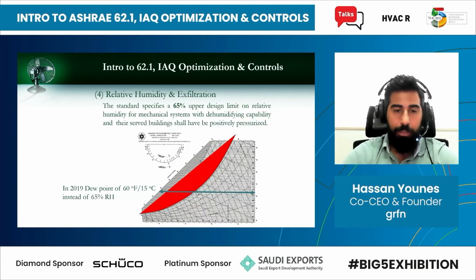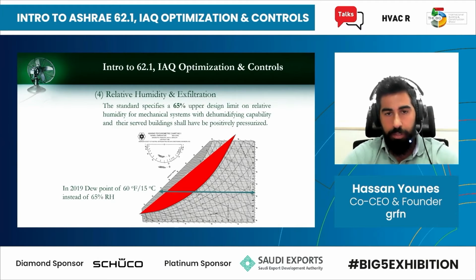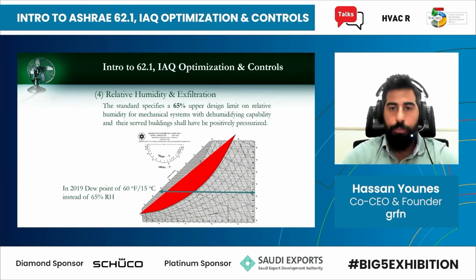That should hold during occupied and unoccupied hours, because you don't want mold to thrive even during non-occupied hours. So at any point in time, the dew point should be below 15 degrees C. Additionally, the building should be positively pressurized if you have any dehumidification happening. So if you have any condensation happening on the coils, the building should be positively pressurized. You don't want humid outside air to go inside the building and cause condensation and high humidity levels.